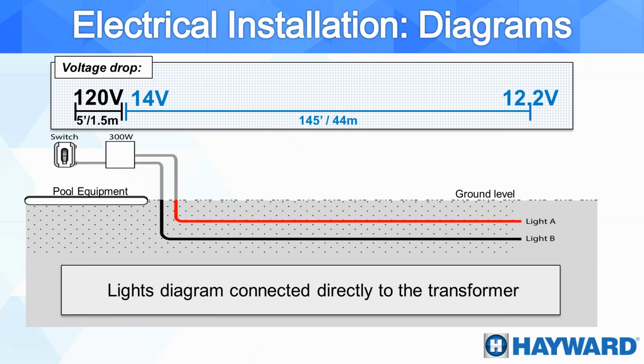Here is another example of installation. In this case, we're going from our switch. Remember, this can be a standard light switch, or it can be a ColorLogic light controller. From the switch to the transformer, and then from the transformer, we're coming out directly to the lights. In this case, we are not using a junction box, but coming out of the transformer, we can see again the 145 feet max in order to get at least 12.2 volts at the light.